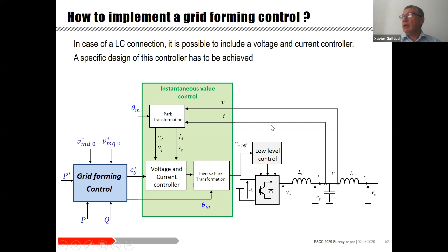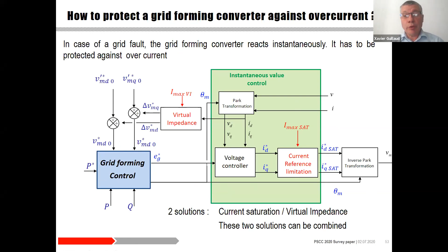In case of a grid fault now, the grid forming converter reacts instantaneously due to its voltage source behavior. However, it has to be protected against overcurrents. Now, there are two solutions: either a limitation of the DQ reference here, or the integration of a virtual impedance in the definition of the voltage. A third solution is a combination of both solutions to take advantage of the benefits of each.